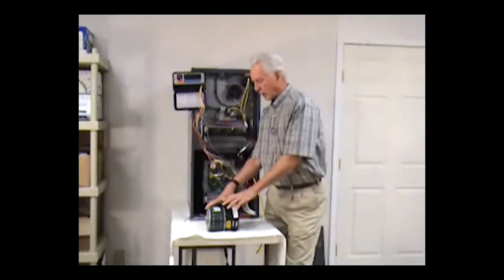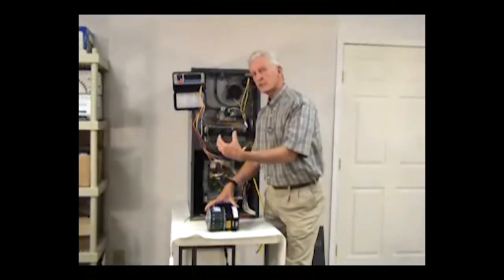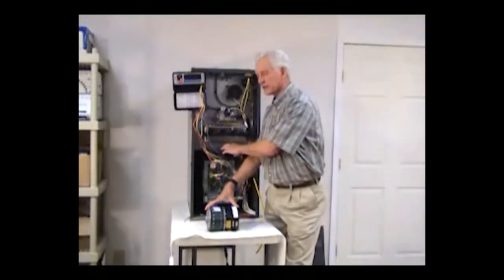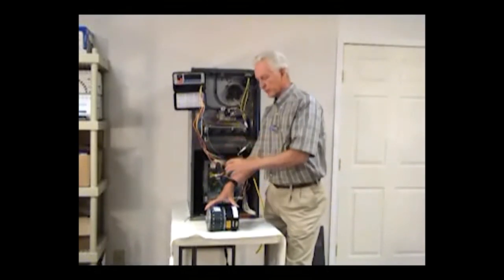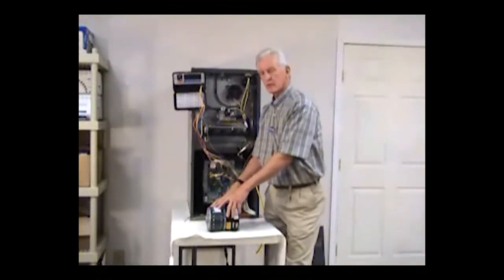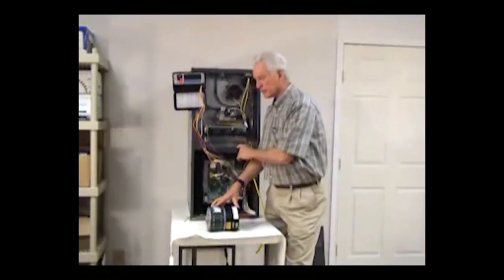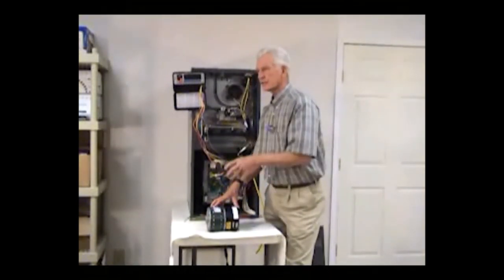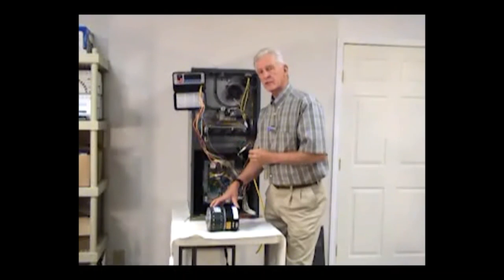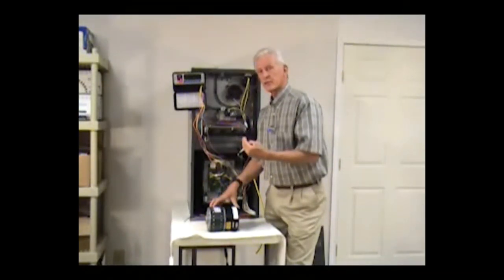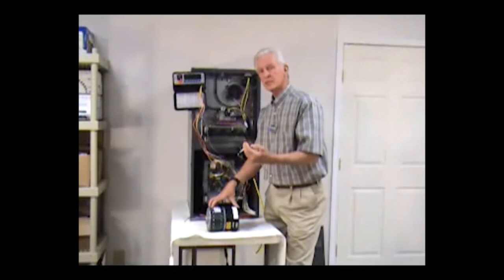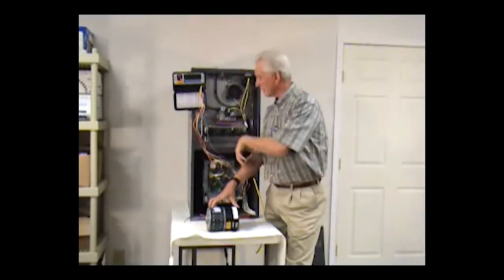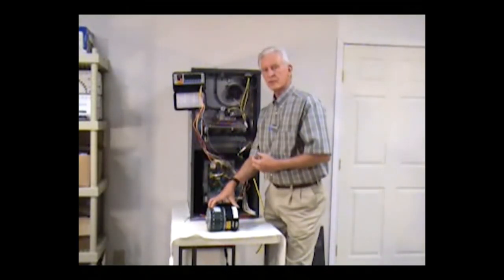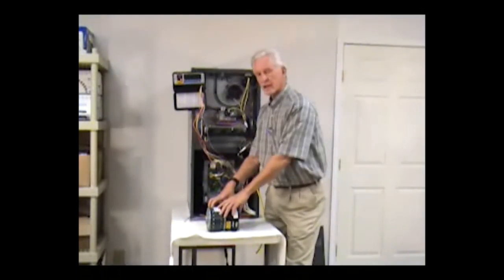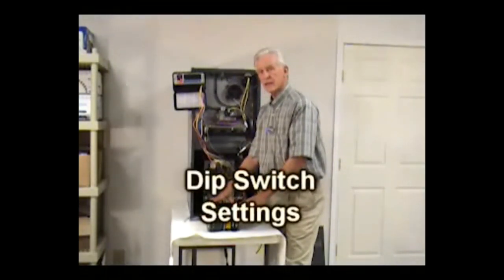And so this module is specific to that motor, and that combination is specific to either a furnace or an air handler. Also, taking from manufacturer to manufacturer, even though this manufacturer here might have a half horsepower motor in it, and the module that they have applied to that air handler, that combination will not fit in another manufacturer's air handler and give you the specific CFM ranges that you're looking for. No furnaces are built the same with the same static ranges on them. So the programming is completely different and specific to each manufacturer's piece of equipment.